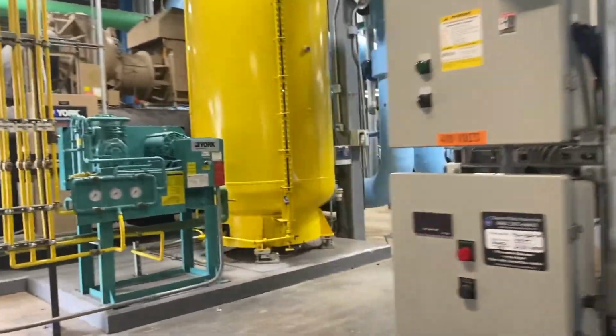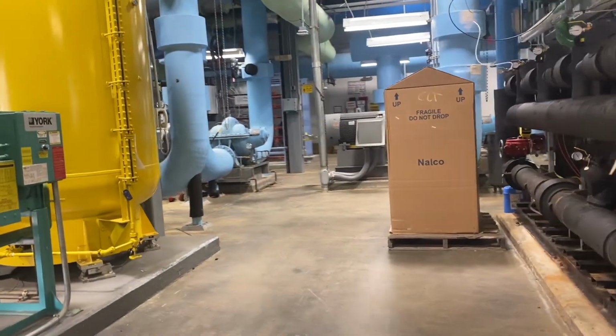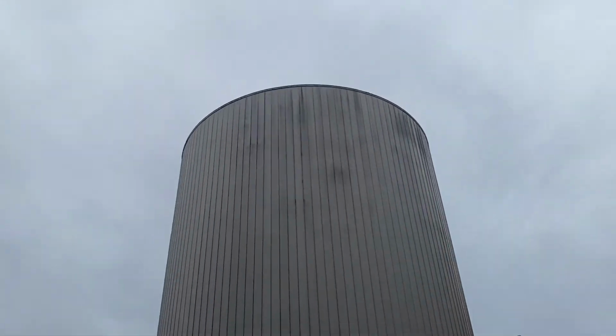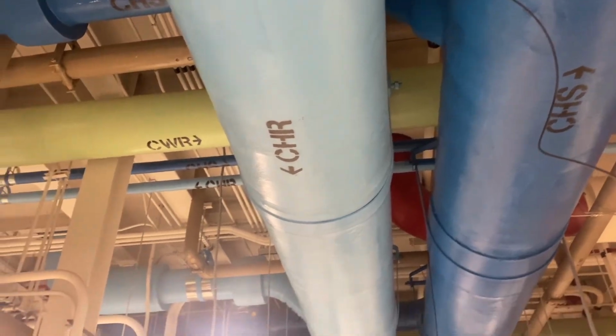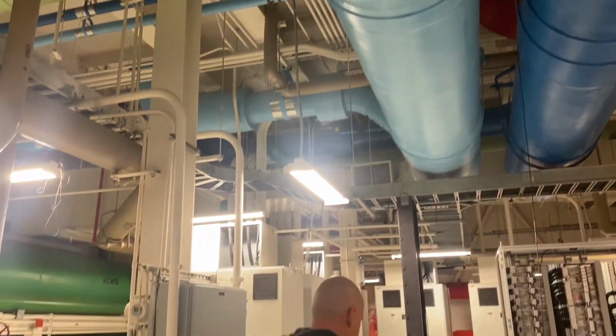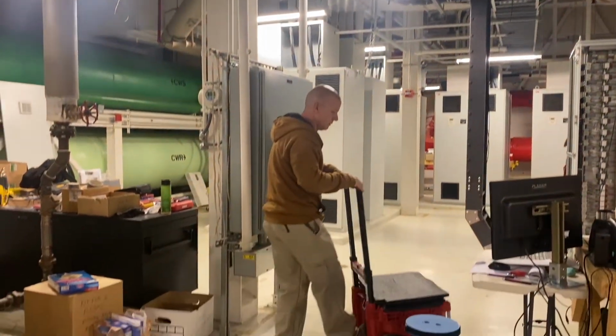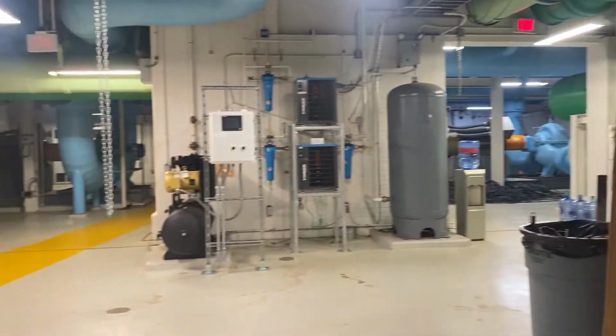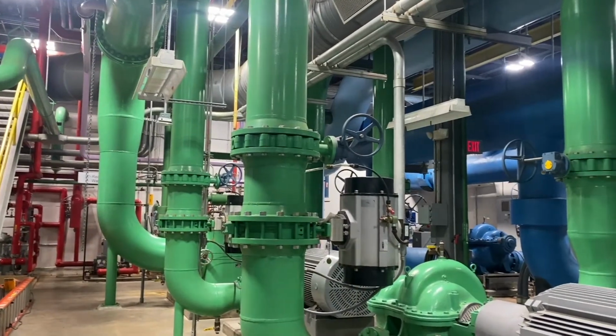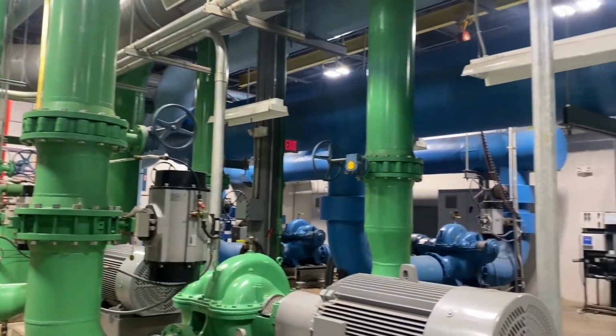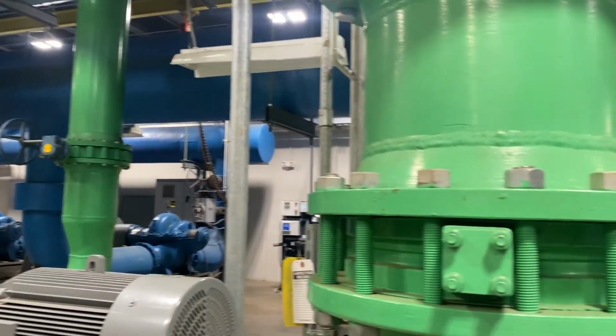The system has approximately 44,000 tons of installed capacity, a 5 million gallon thermal energy storage tank, and 9.4 million gallons of total system volume. Inside the chiller plants, there is large color-coded piping running throughout the building. Each color serves a purpose. For example, purple is reclaimed water, red is steam, green runs between the chillers and the cooling towers, and the blue piping contains the chilled water. The darker the shade of blue, the colder the water is.